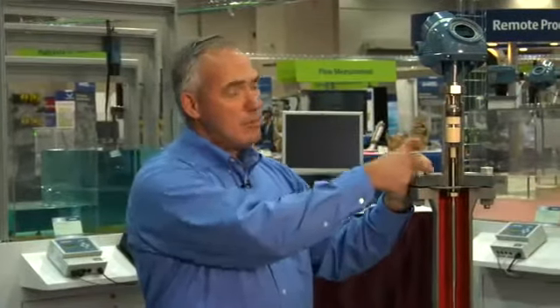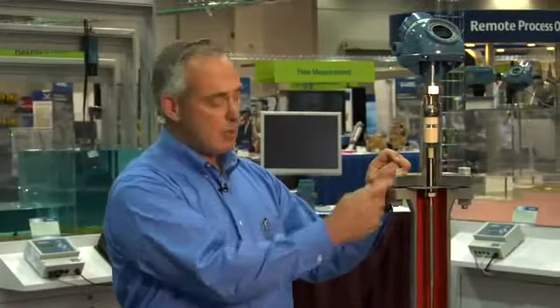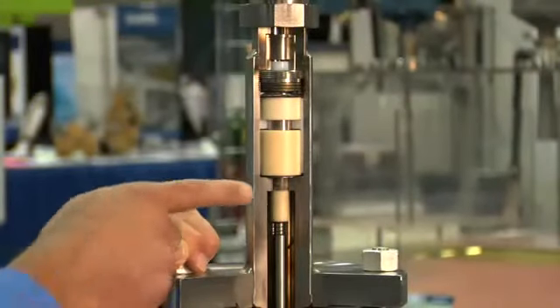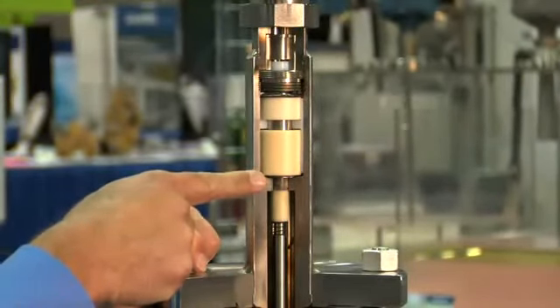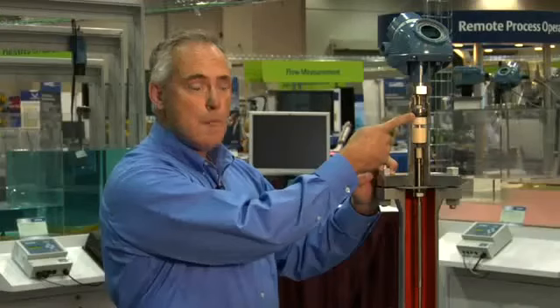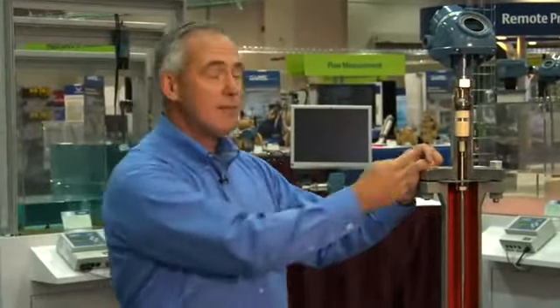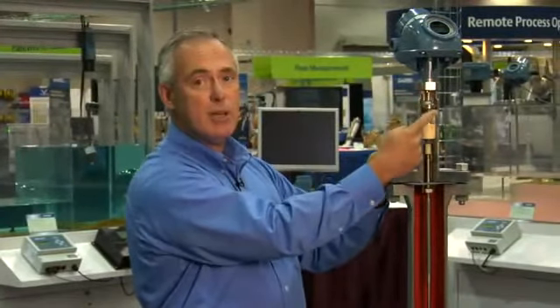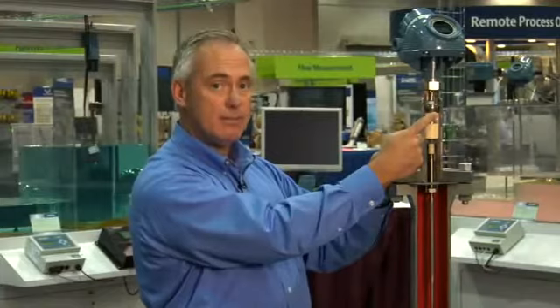The next feature I'd like to point out on the 5300 is its seal construction. As we mentioned, these vessels that we're measuring level in are high pressure and high temperature applications. So safety is paramount when we're looking at putting a device into that environment. What I'm showing you here is the high pressure seal that keeps process here and not here while we make this measurement. This seal is a twin seal design, and what you'll see is there's a primary seal here and there's a secondary seal here. If the primary seal fails, the device will malfunction. You won't be getting a measurement from the device. However, steam won't escape because it is being held in by the secondary seal located here.